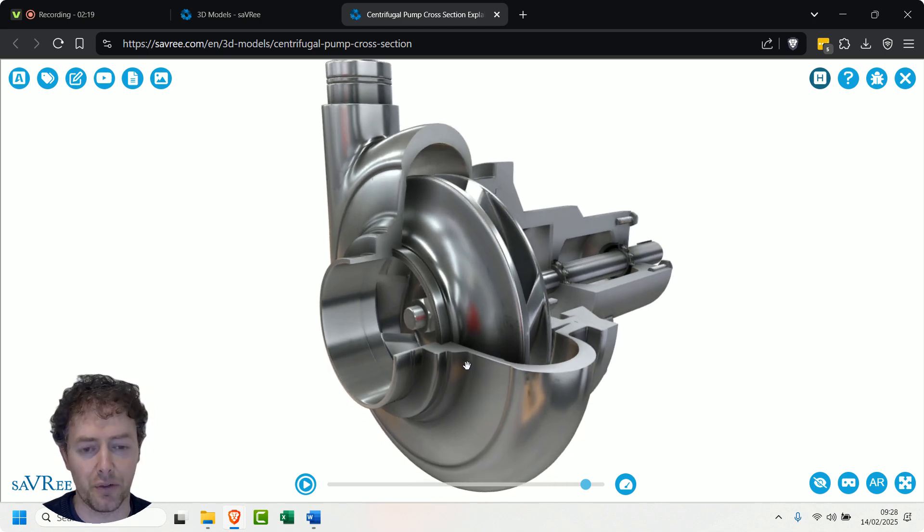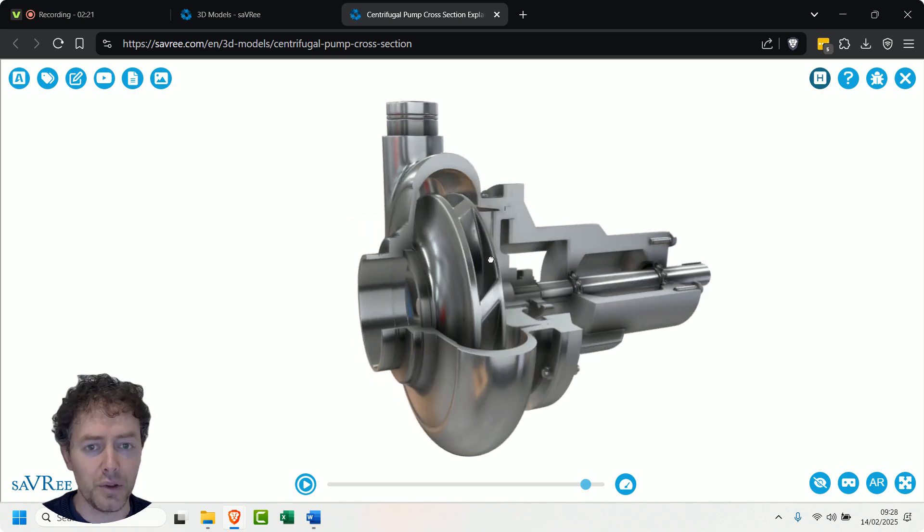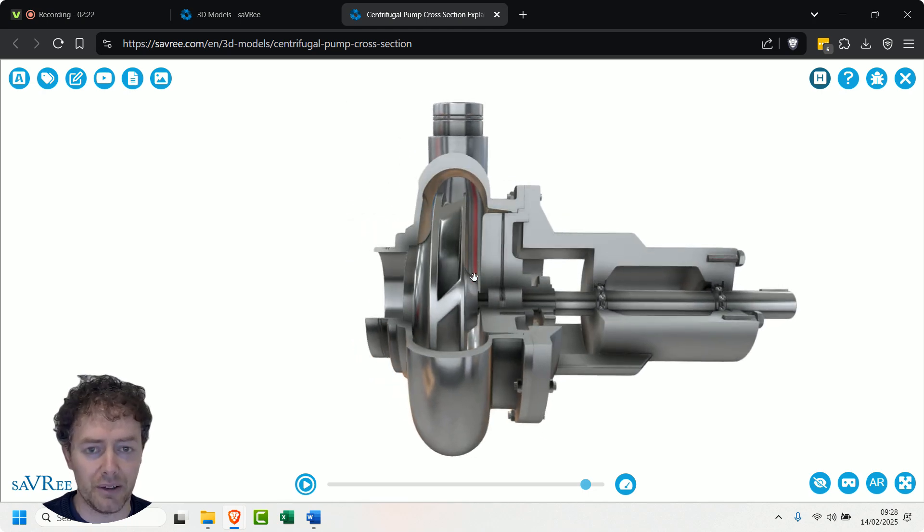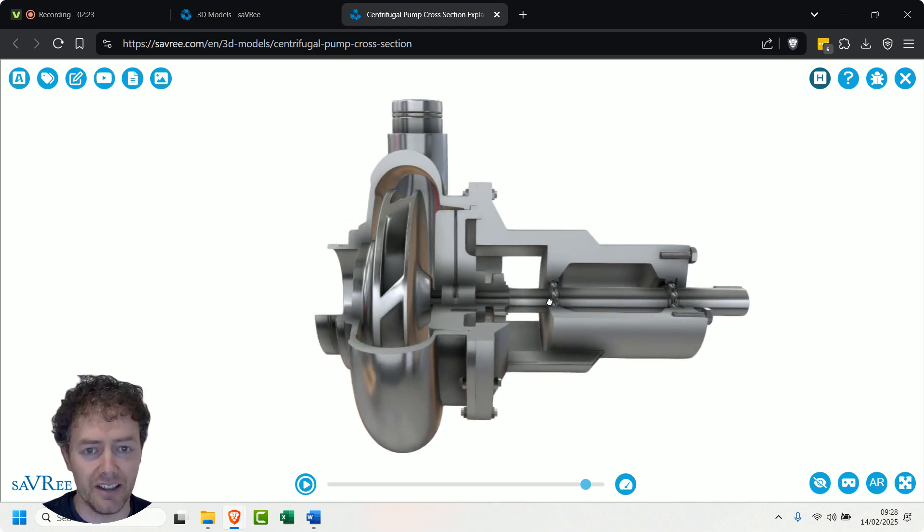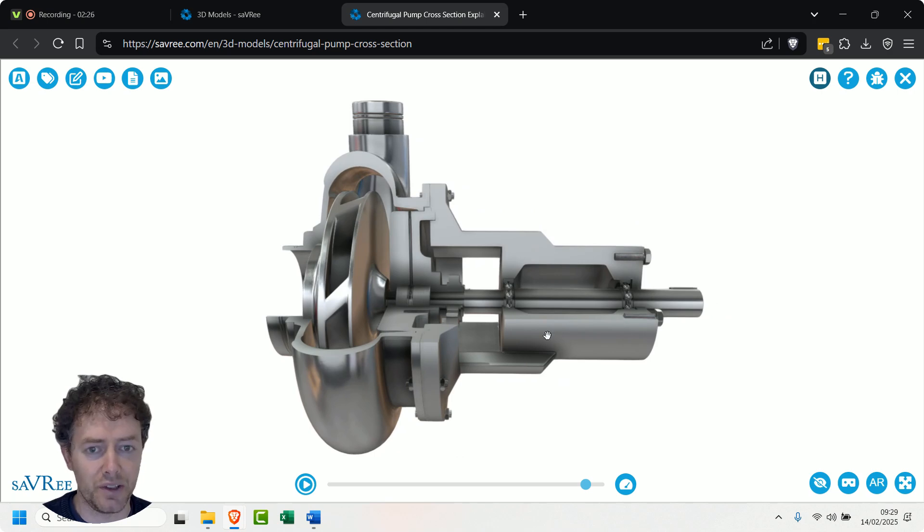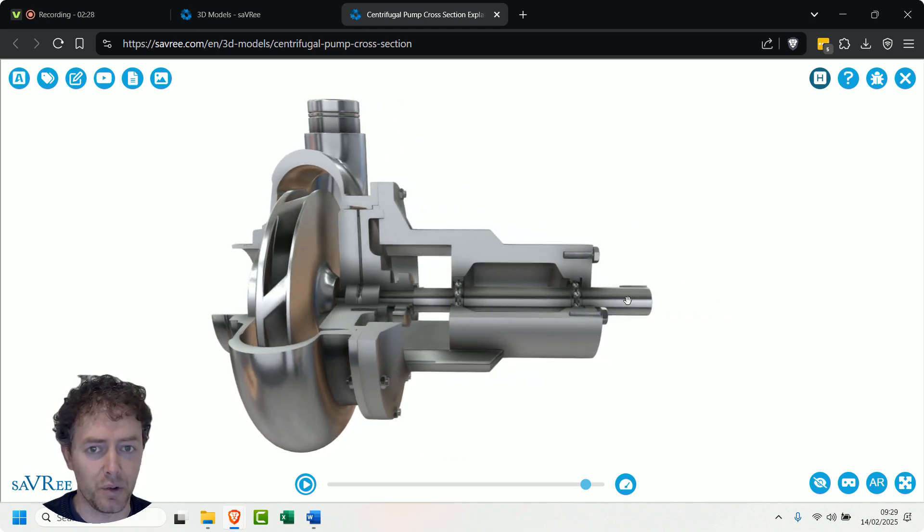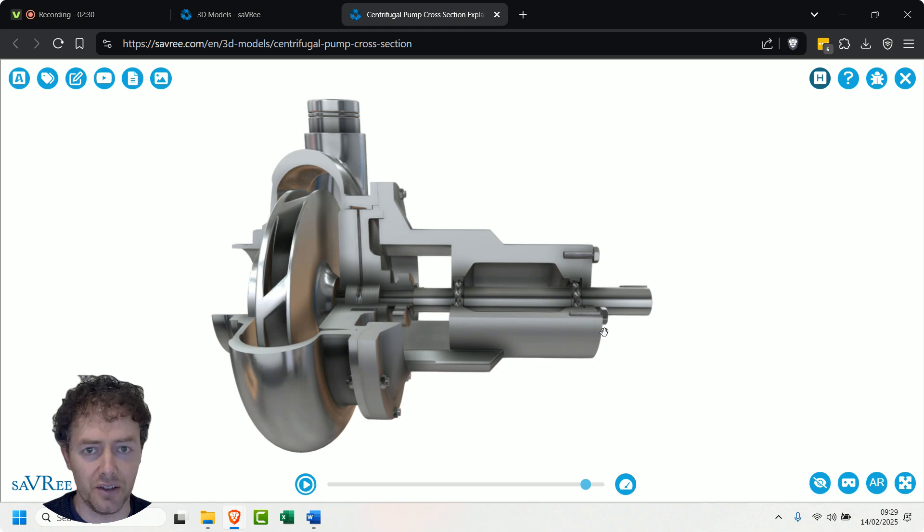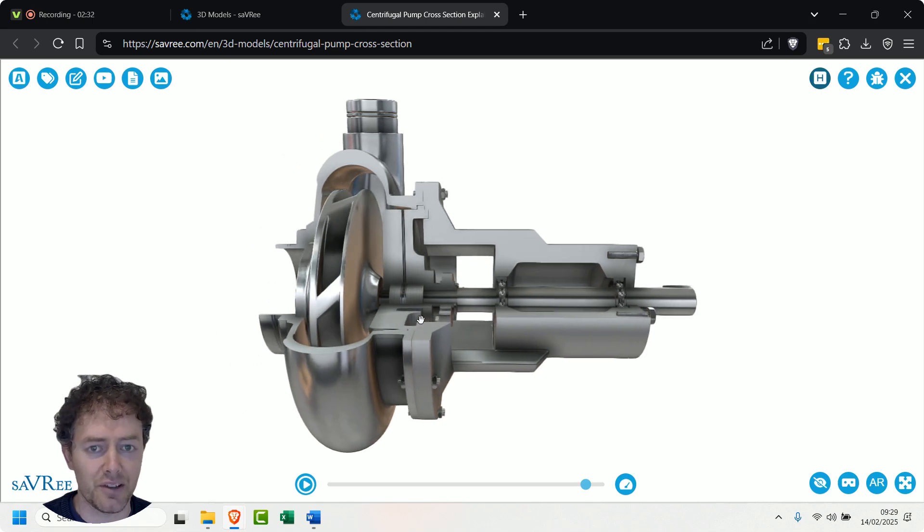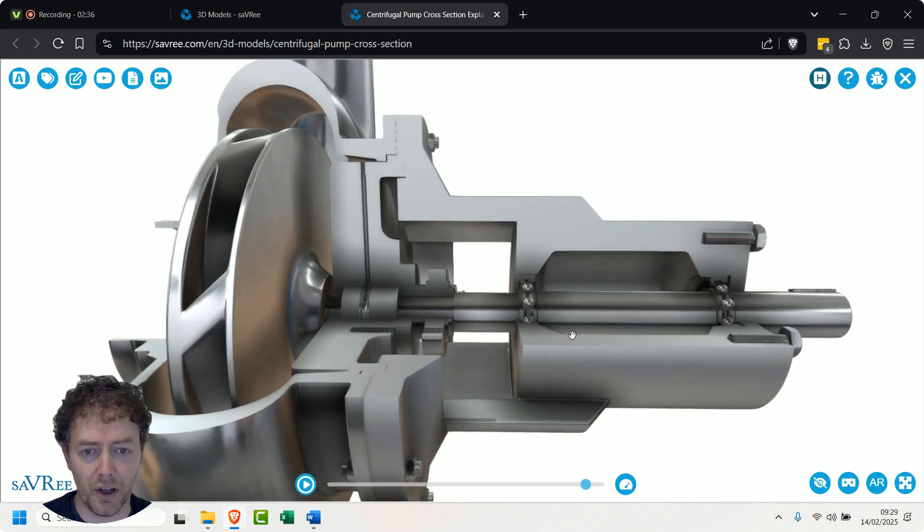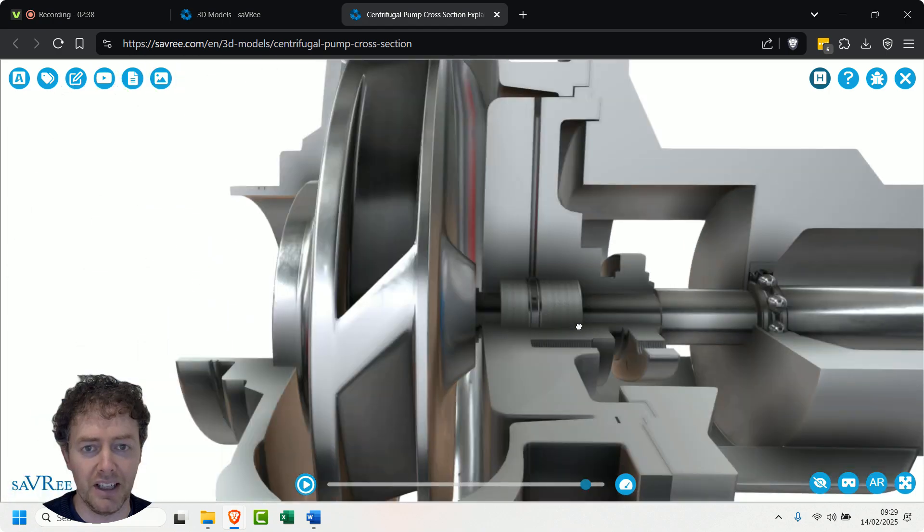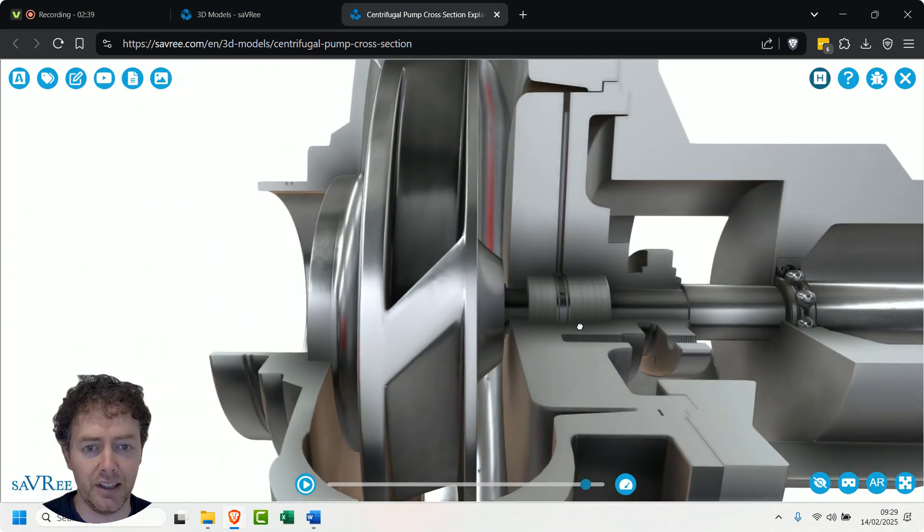While we're talking about that, let's have a look at this design. This design is supported at one end, it's supported on this side, and that's because it's an overhung centrifugal pump. That makes it an overhung pump because the impeller's hanging over here where it's supported over here.